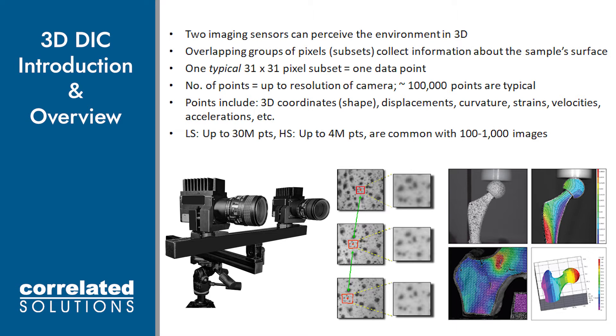Currently, low speed cameras can have up to roughly 30 million points in an image, and high speed cameras can have up to about 4 million points in an image. We aim to get about 200 images for most dynamic and quasi-static applications, and a few thousand images for vibration analysis. This is all highly dependent on the application, what the user wishes to measure, and desired measurement resolutions.